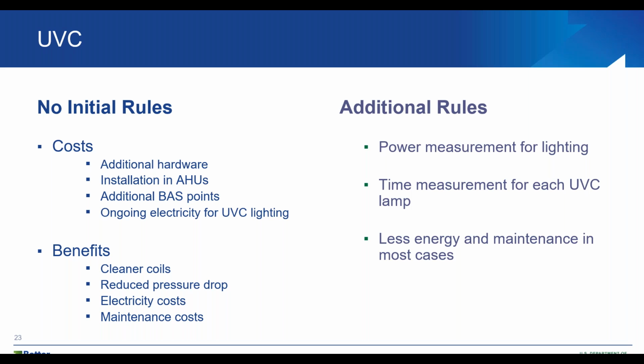Another would be time measurement, because they only last so long. I believe, depending what you're using, could be a year and a half, and you want to make sure you replace this before it's no longer effective. This is not something you want to wait till afterwards. Some filters you maybe will wait a little longer, but I'd want to make sure the UVC is done early, if anything. So in most cases, UVC will use less energy, but you also have to have the correct FDD in place to make sure it's operating the way it's supposed to. And again, this is something that you need to coordinate with the facilities person, the BAS vendor, and your EMIS vendor to make sure when it's installed, when the controls are installed, and the rules are written. So it's all operating in synergy.